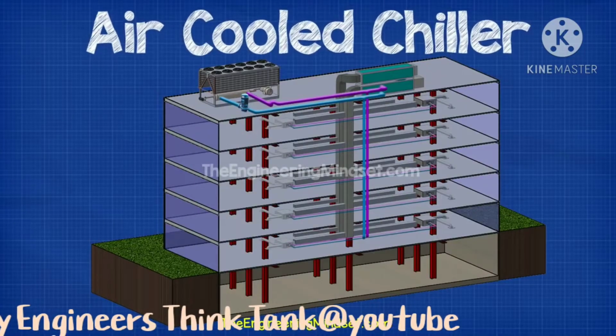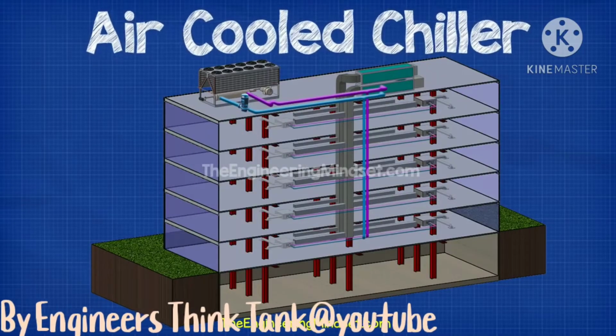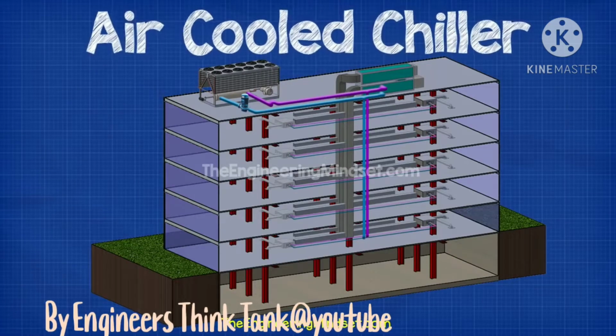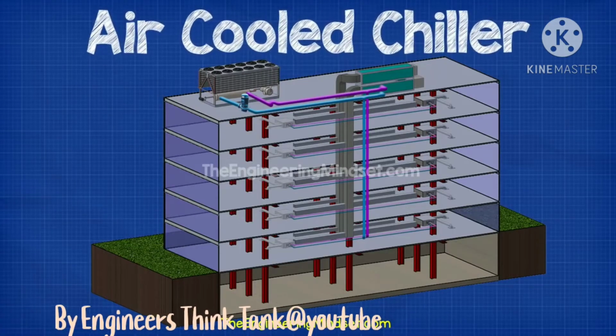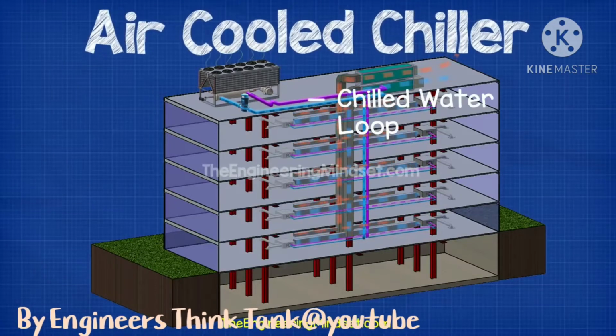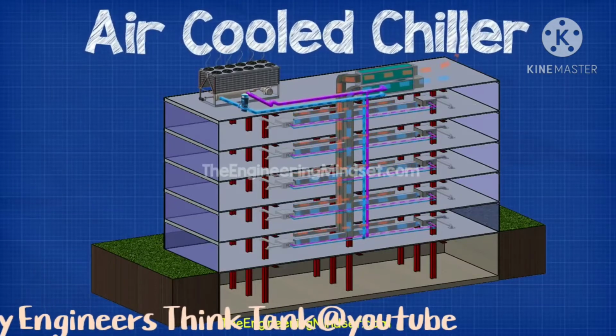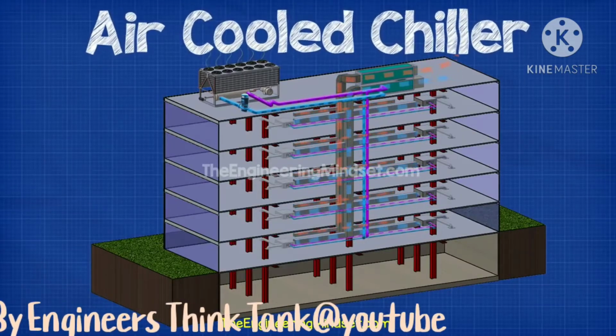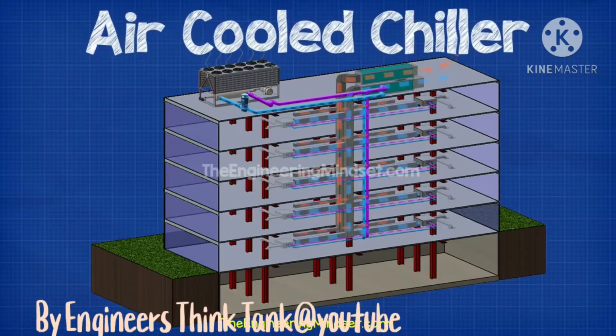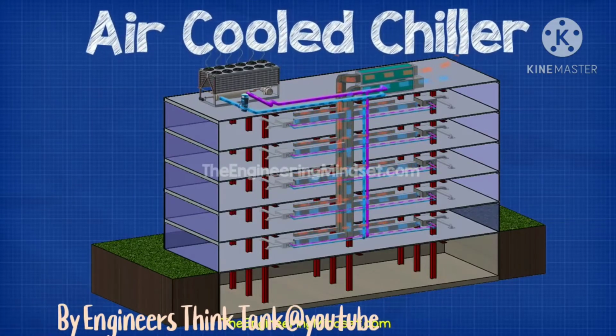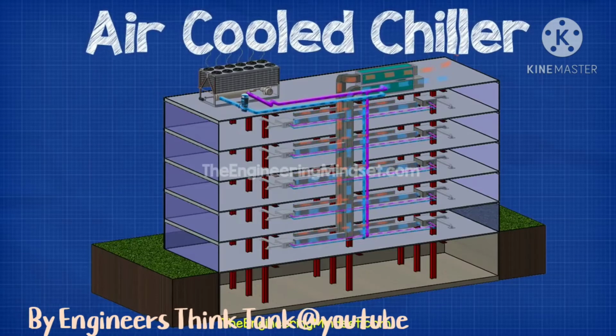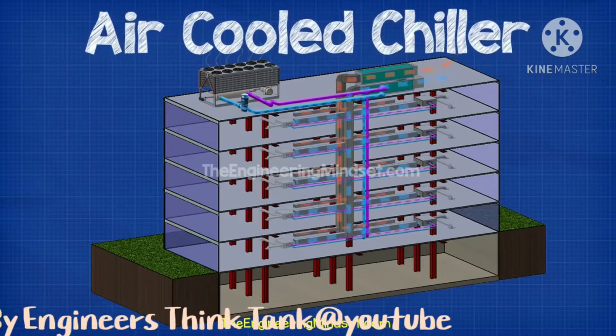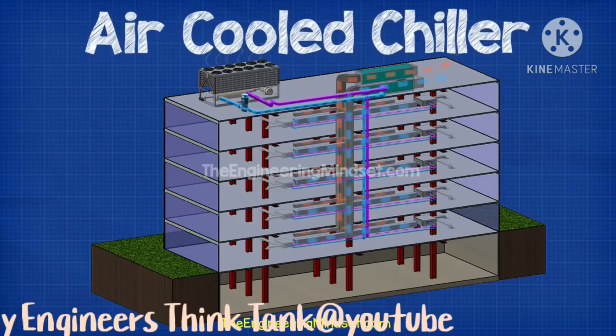Air-cooled chillers. Air-cooled chillers are typically located on the roof of the building or outside, say in the car park. The air-cooled chillers also generate chilled water, which is pumped around the building to air handling units as well as fan coil units, etc., in order to cool the building and pick up unwanted heat. The air is forced to circulate around the building and local space and will pass across heat exchangers within the air handlers and fan coil units.